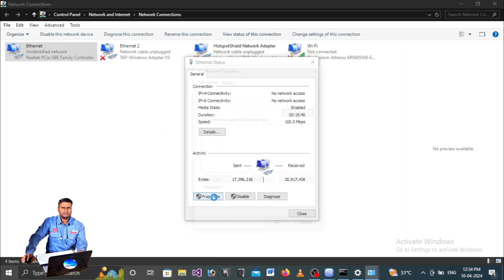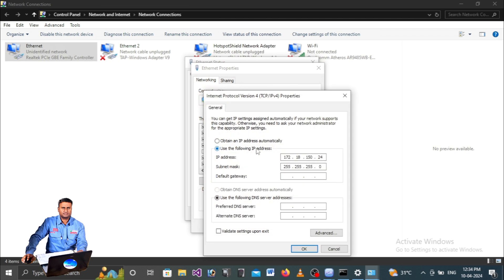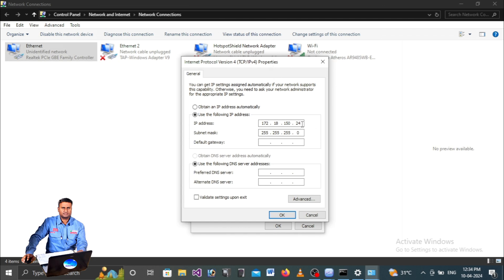In the IPv4 properties, double-click to see the IP address. The problem is that the laptop IP address and relay IP address are the same - they must not be the same. The relay IP address should be lower, and the laptop IP address should be higher. For example, set the laptop IP address to 200 - it must be greater than the relay IP address of 24.